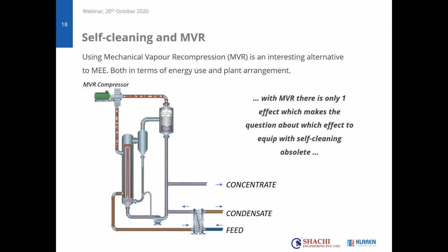But when looking at MVR, one discussion is solved, and that discussion is about which effect, because in an MVR there is only one effect. And how does an MVR work? Well, in fact, the reason why you need much energy for evaporation is that you need to convert water from the liquid phase to the vapor phase. And then you need to add the latent heat. But at the moment that you can recover this latent heat, of course you benefit. That's why you have multi-effects. You use the vapor multiple times. But with a multi-effect, still at the end, some part of the vapor is going to the condenser. With an MVR, all the vapor that you generate is condensed again. So this total heat content is recovered. And that's why an MVR, in the core of the physics, is a better concept.